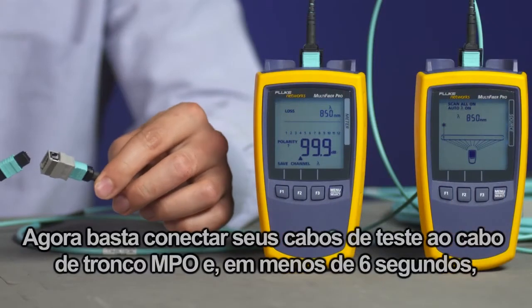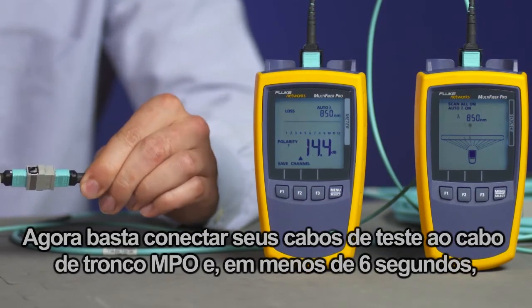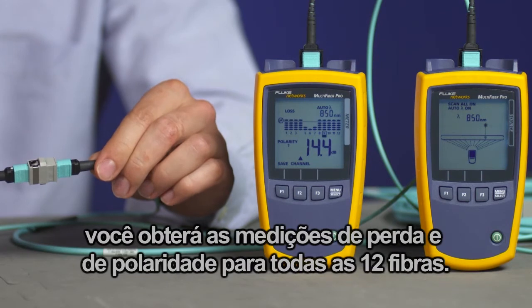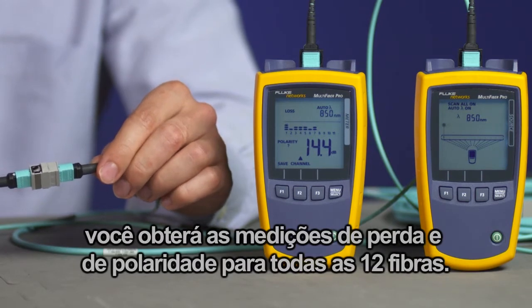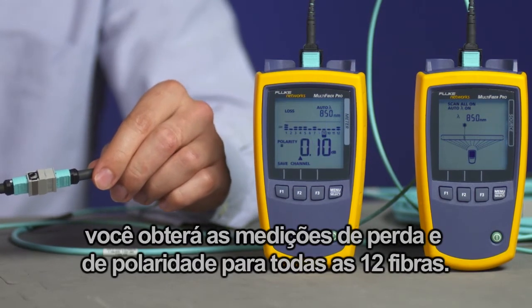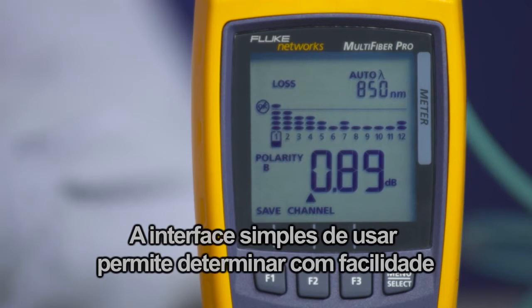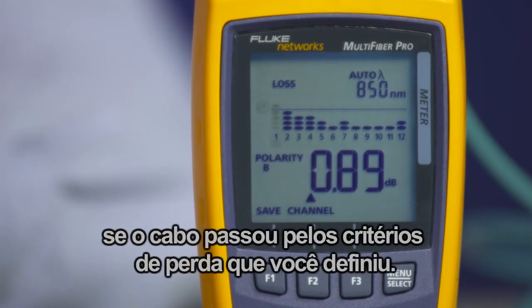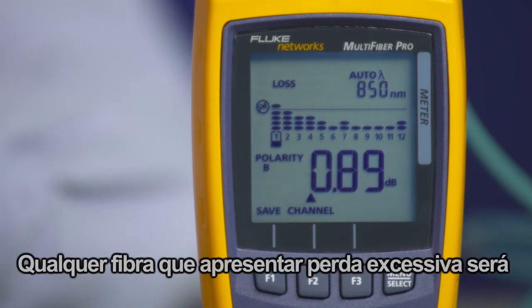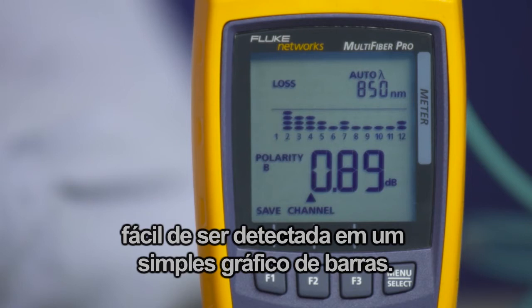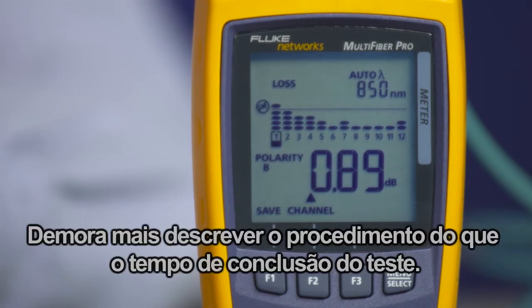Now simply connect your test cords to the MPO trunk cable, and in less than 6 seconds you'll have the loss and polarity measurements for all 12 fibers. The simple user interface allows you to easily determine if the cable passes the loss criteria you set. Any fiber that has excessive loss will be easy to spot in the simple bar graph. It takes longer to describe the test than it takes to complete.